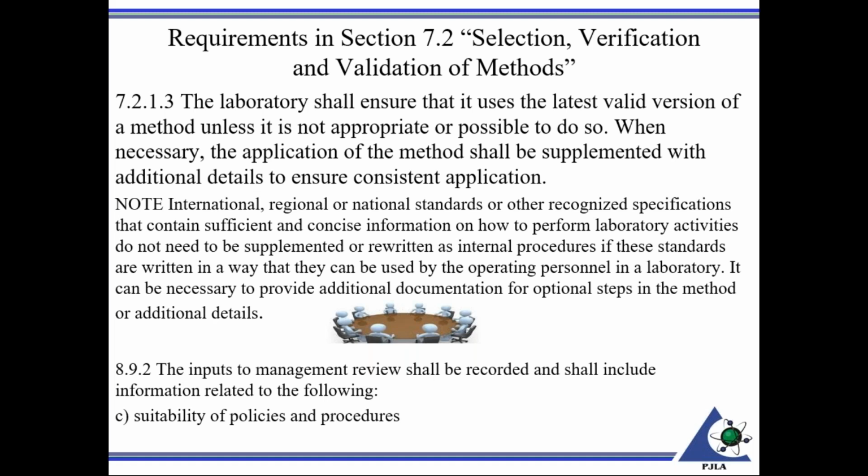So basically what that's saying is you can adopt a method, ASTM E898, for example. That's a quite detailed method. You can adopt that as your procedure. You don't have to rewrite it or write it internally. However, you may elect to write a method based on the nationally recognized method, an internal SOP that is easier for your individuals to utilize when performing laboratory activities.